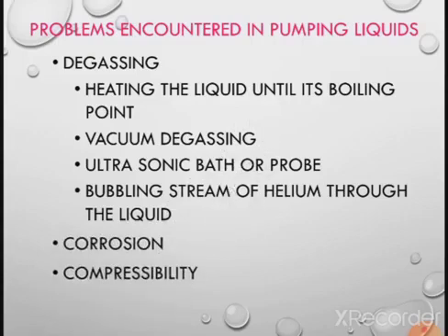The next problem is corrosion. When the mobile phase comes into direct contact with the pump, it may cause corrosion, and due to this corrosion it may cause contamination. Another thing is compressibility. Some liquids are compressible in nature, and due to this they give a different flow rate. So these are some problems in the pumping.